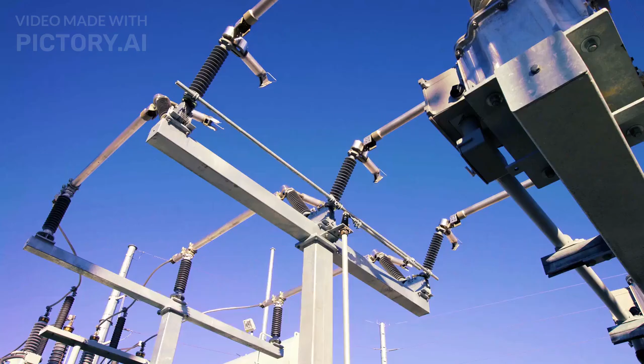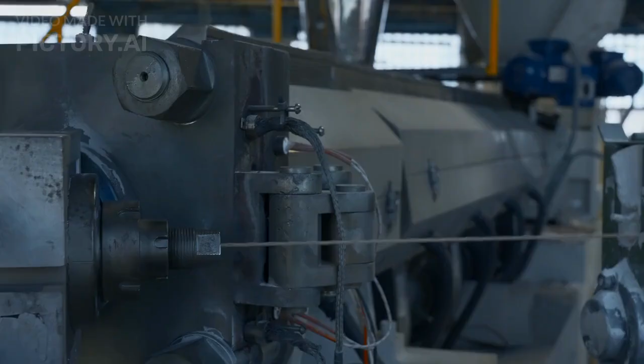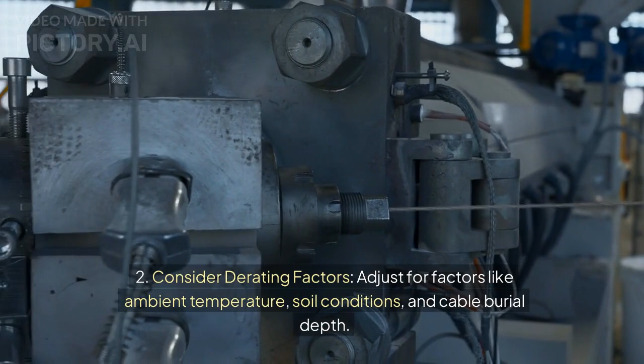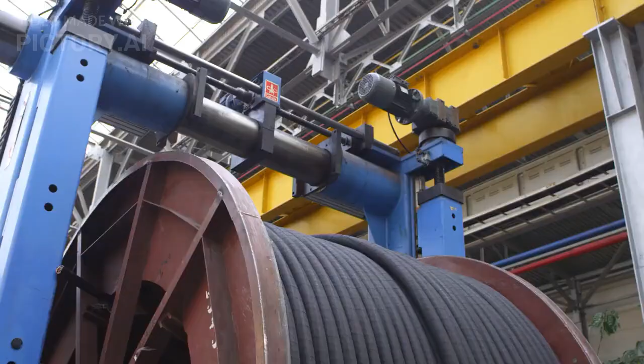7. Check ampacity. Ensure the cable can handle the current without overheating. Refer to ampacity tables for the selected cable material and installation conditions. 8. Consider derating factors. Adjust for factors like ambient temperature, soil conditions, and cable burial depth. 9. Final selection. Choose the cable size that meets the voltage drop and ampacity requirements.